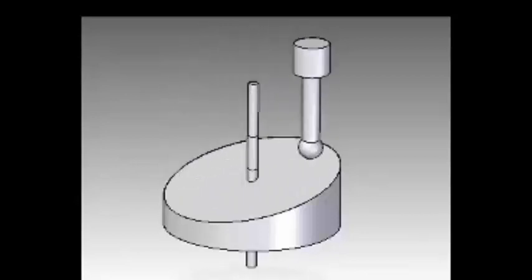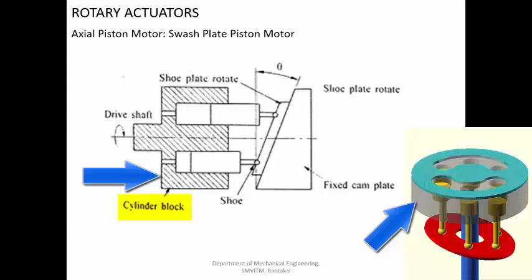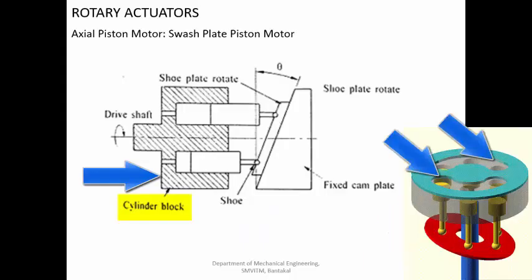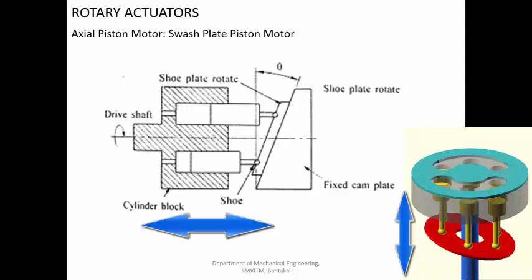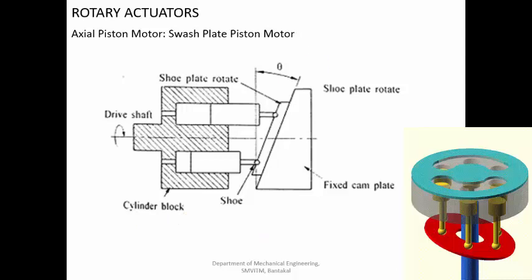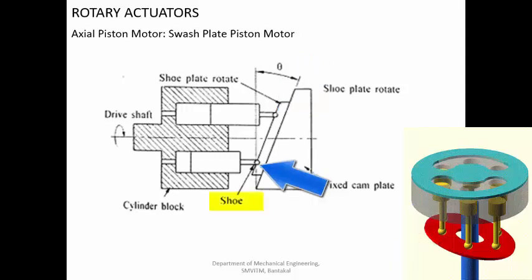So how does the piston rotate? You are having a cylinder block here. The cylinder block will have multiple holes — maybe 9, 7, or 11 holes. In each of these holes you will have a piston which can reciprocate up and down. Now the end of the piston rod is pressed against an inclined surface, and you are having a piston shoe here in order to reduce the friction. This entire cylinder block can rotate.